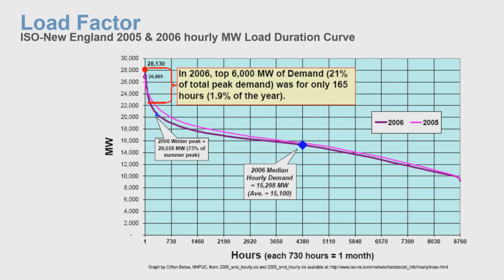operating. A little further inspection of the graph shows that the top 6,000 megawatts of demand, which represents 21% of the peak, was only used for 165 hours. 7 days per week times 24 hours per day is 168 hours. So 21% of the total generating assets were used less than 1 week per year.